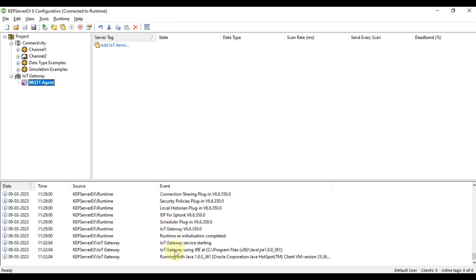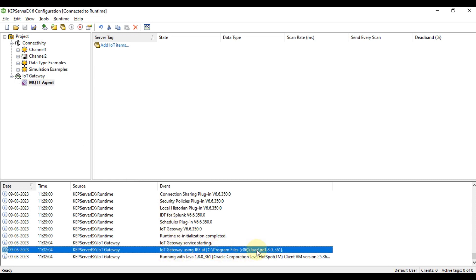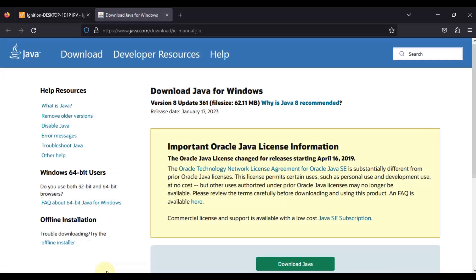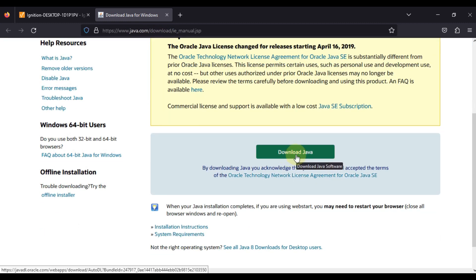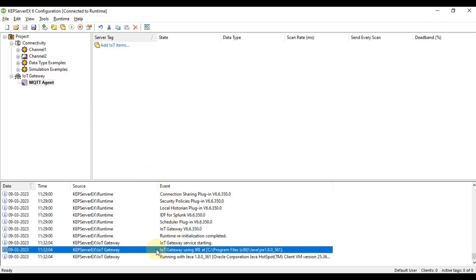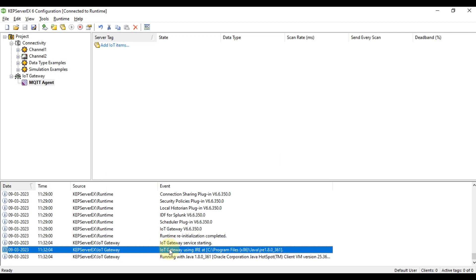You can see the IoT gateway is using JRE at some location. If your IoT gateway gives an error that JRE is not installed, go to www.java.com, download and install Java, then restart KEPServerEX — the error will not appear again. I faced that error myself, installed Java, and then the IoT gateway worked properly. The MQTT agent has now been created successfully.